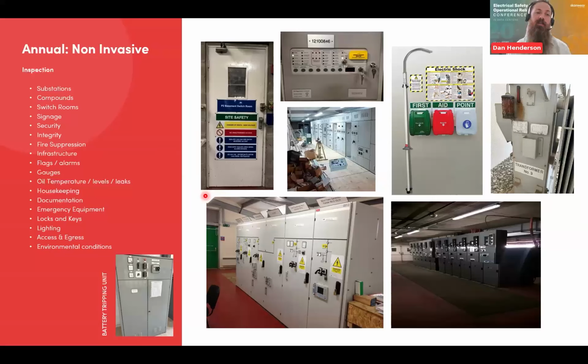The infrastructure, and again, this is massively overlooked, but things like the roof condition, the integrity of the walls, the fire stopping. So if you've got a fire in that location, you don't want it to go into somewhere else. Down pipes linked in with the roof and the ceiling. If you've got any water systems above or it's external, any signs of leaks, anything that's going to give rise to danger, like water ingress into a substation, is all bad news. I'm sure we'll all agree. But the infrastructure is a key one.